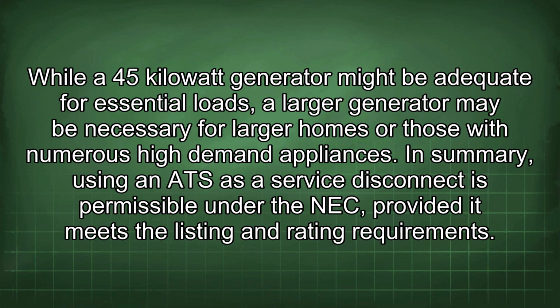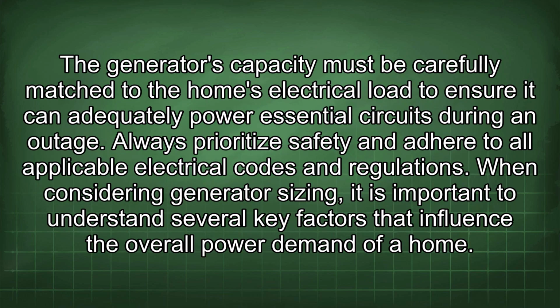In summary, using an ATS as a service disconnect is permissible under the NEC provided it meets the listing and rating requirements. The generator's capacity must be carefully matched to the home's electrical load to ensure it can adequately power essential circuits during an outage. Always prioritize safety and adhere to all applicable electrical codes and regulations.